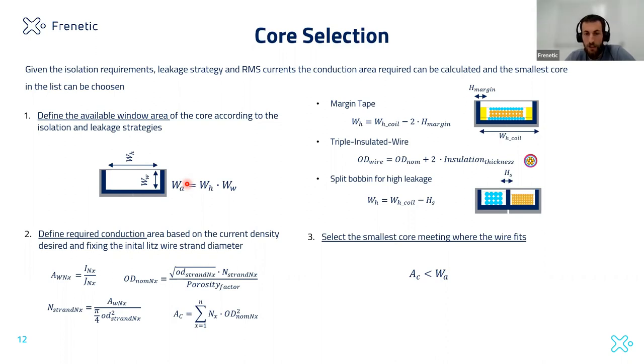Now we need to take out those cores where the wire will not be able to fit. Okay, so where, let's say, the window will be too small to fit the wires. So how can we do this? Okay, we have an available window space, which is here, which is given by the size of the window area. So if this is the core, this is the coil former, this is the height of the coil former, this is the width inside the window. So this is the available area that we have. And now we need to see if our wires fit or not.